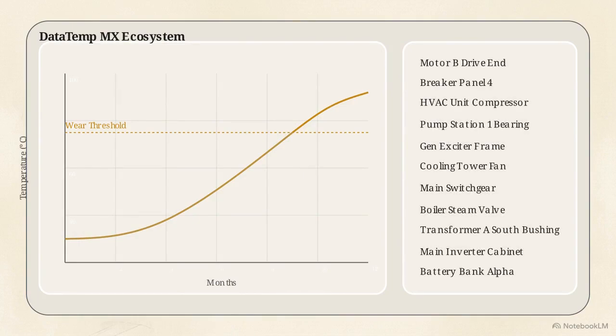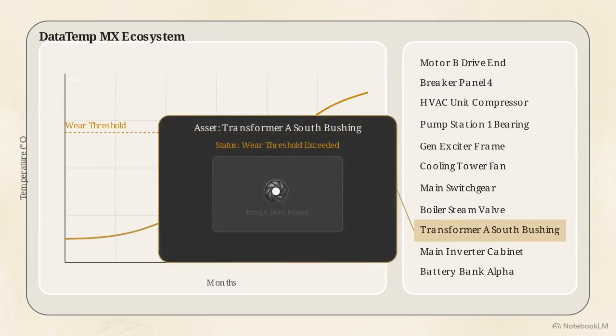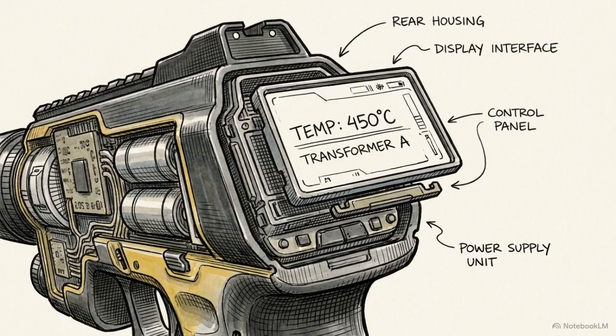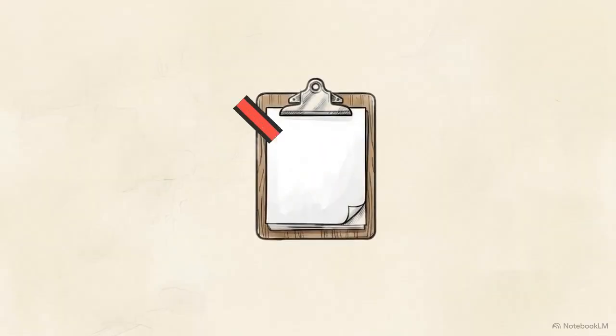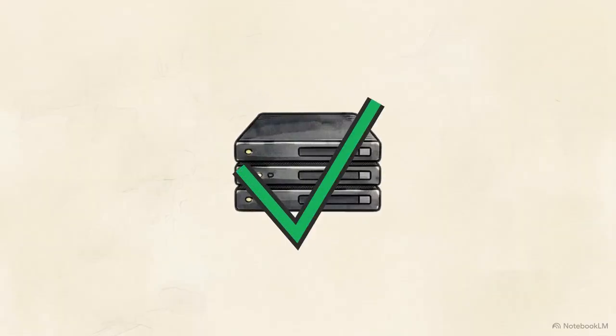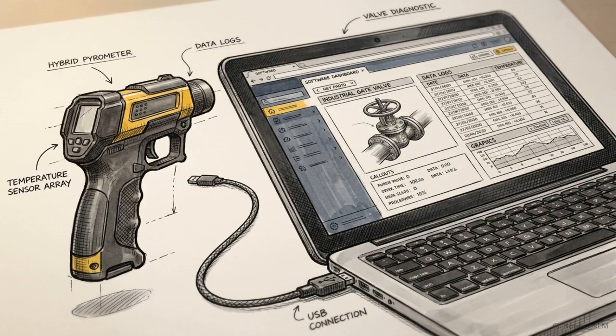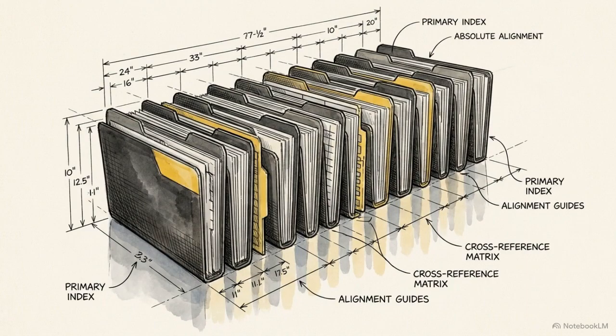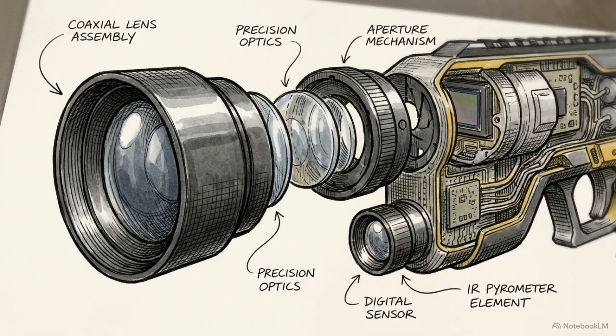The software allows managers to preload up to 100 highly specific location names, such as Transformer A South Bushing. As the technician walks the route, the MX6 displays exactly which component to measure next, effectively eliminating the risk of manual data entry errors. By hardwiring the data capture to the photographic evidence and routing it through structured software, the MX6 replaced isolated analog readings with a rigorous, verifiable digital audit trail. That audit trail only works if the initial thermal data is accurate.